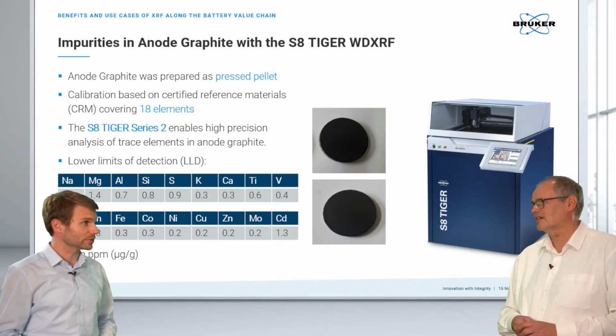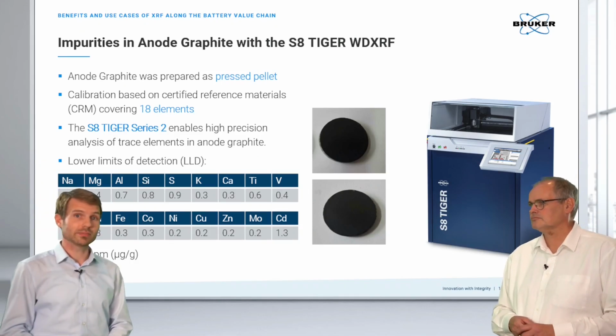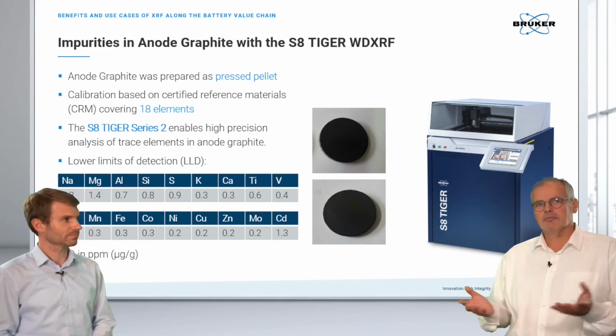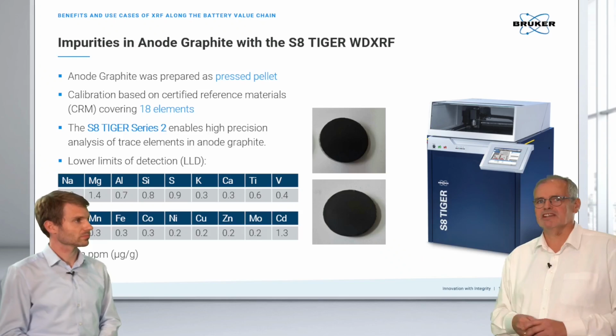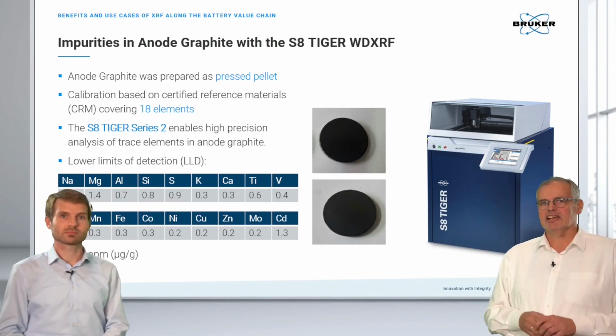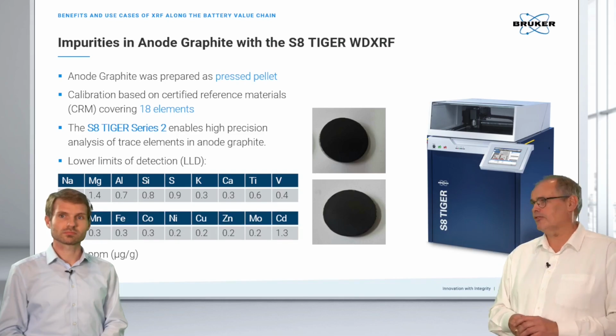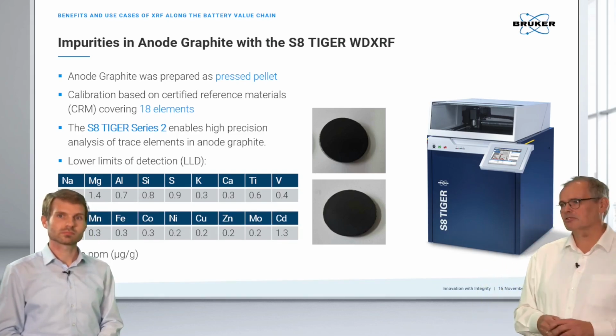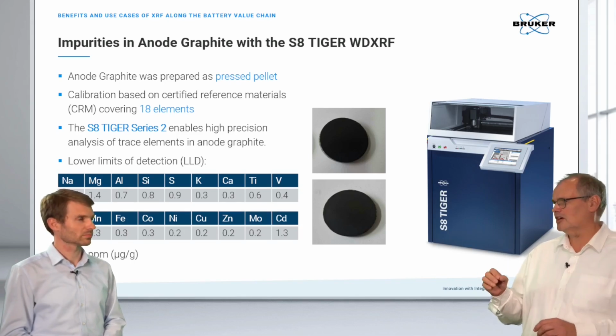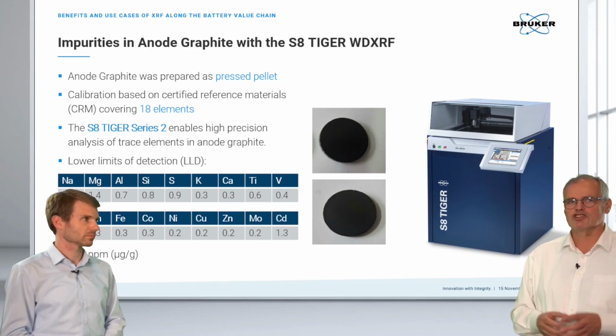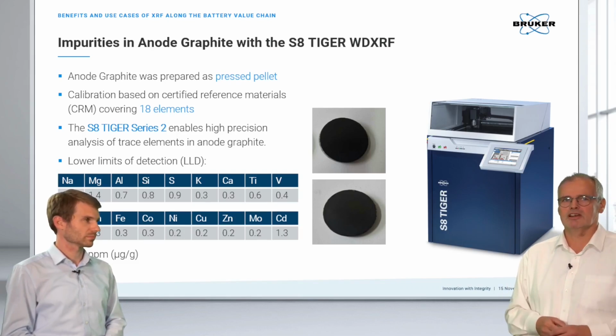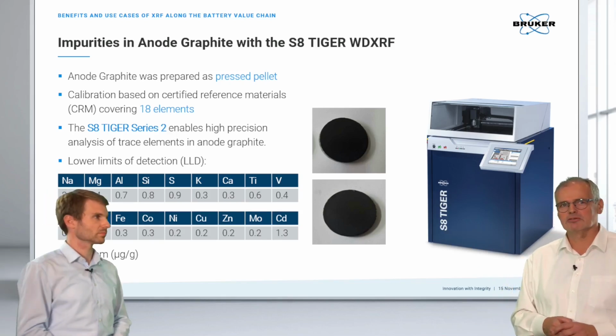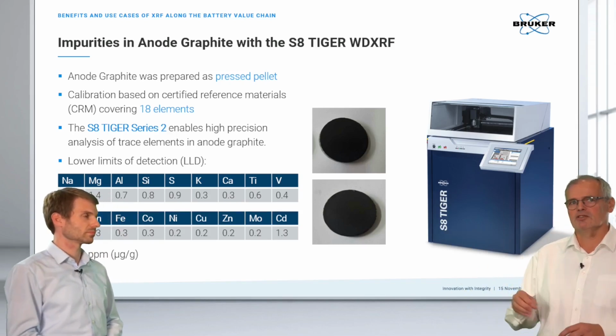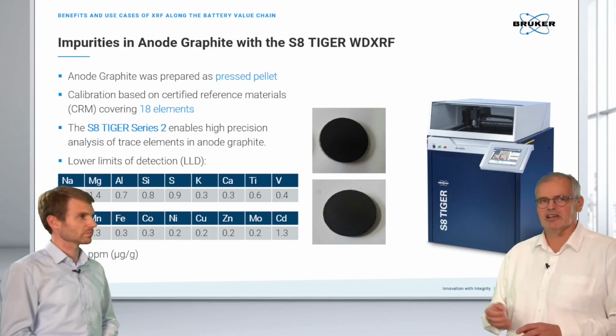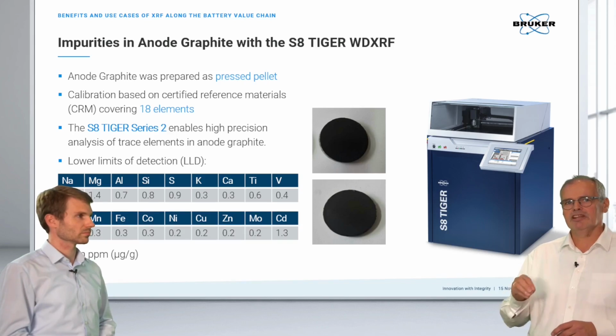Maybe a few words about anode graphite. That's one of the materials that you might receive. And this is something that you can measure quite well on the Tiger, right, Kai? Yeah, we work with 400 watt excitation power with a benchtop instrument. Nevertheless, we also have a floor-standing model which works with up to 4 kilowatts. And the reason is quite simple. For graphite, we look at low 1 ppm detection limits. We want to really understand the impurities, especially elements like sulfur, chlorine, but also copper. They can have a negative influence on the anode, and therefore we need a powerful detection method.